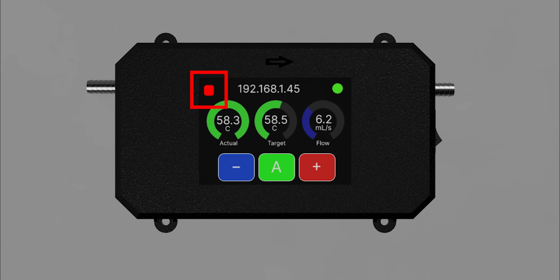It functions as a button you can click to disable all form of flow and regulation control from ATACC. This is useful if you ever need to have ATACC turned on while the water supply is unplugged or turned off, as normally ATACC constantly needs at least a little bit of water at all times, or else it will trigger an emergency shutdown. If the square is red, it means flow regulation is turned off. If the square is black or appears invisible, it means it is not disabled and is operating normally. That is it for the controls on the touchscreen.